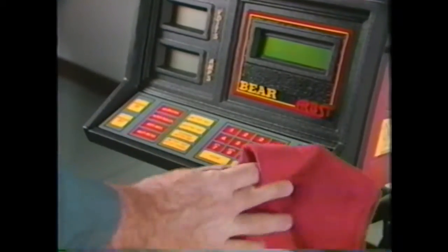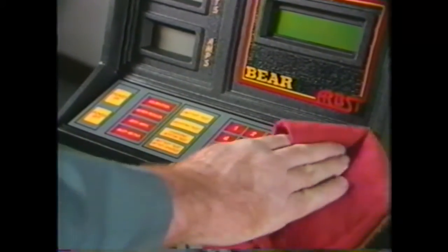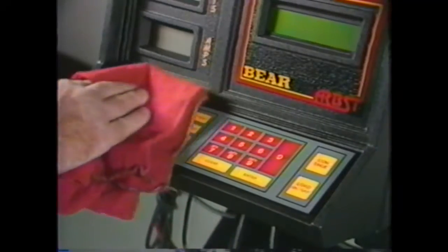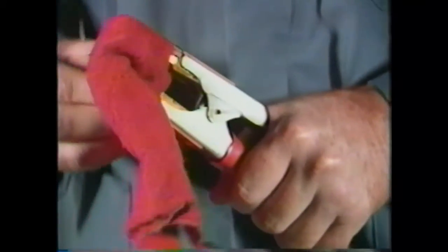Keep the keypad, displays, and outside surface of the tester clean by wiping them with a mild multi-purpose cleaner such as Fantastic or 409. Clean the cables and clamps with a mild multi-purpose cleaner such as Fantastic or 409. While you are cleaning the cables, inspect them for damage. Check and replace as necessary. To prevent deterioration of the rubber, do not use solvents or harsh cleaners on the test leads. Keep the clamp ends clean. Use a small wire brush if necessary. Or if the clamp ends are corroded, use emery cloth to clean the brass.